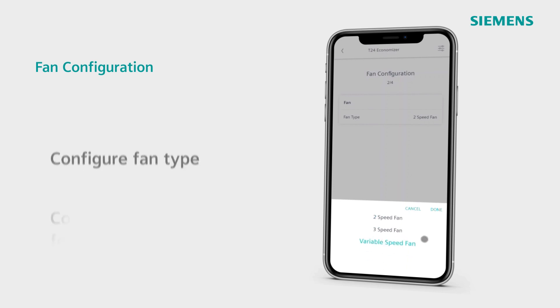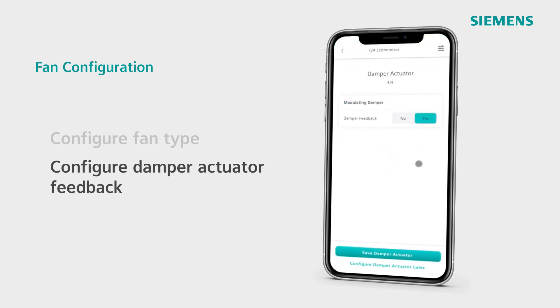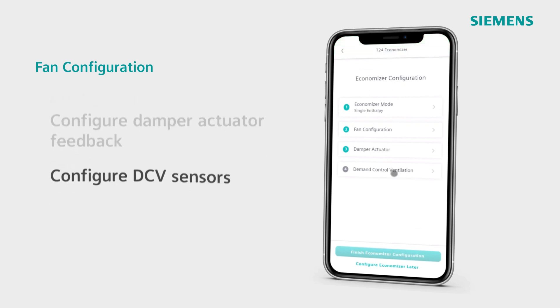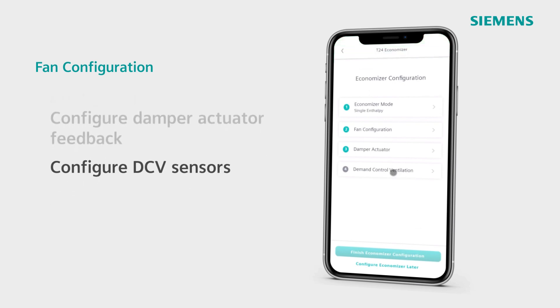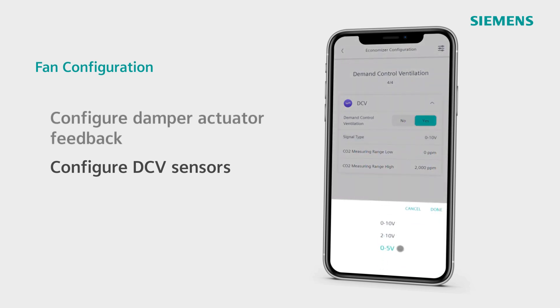Then select the damper actuator to adjust whether there is damper feedback. Finally, for the Economizer configuration, we can configure demand control ventilation, choosing the signal type for your sensor and the ranges you would prefer to keep your CO2 measurements within.